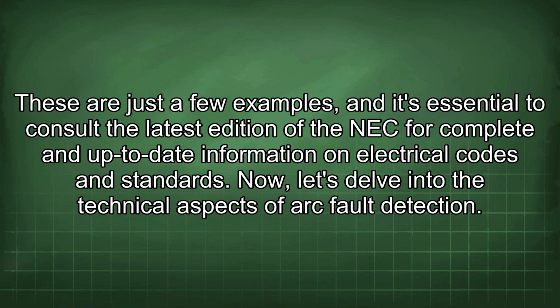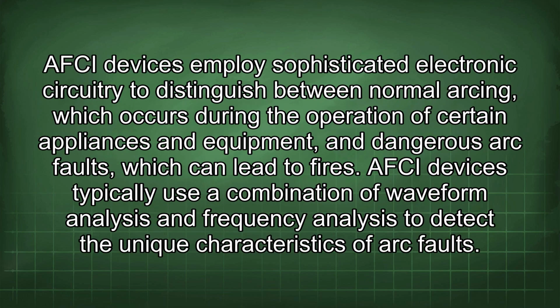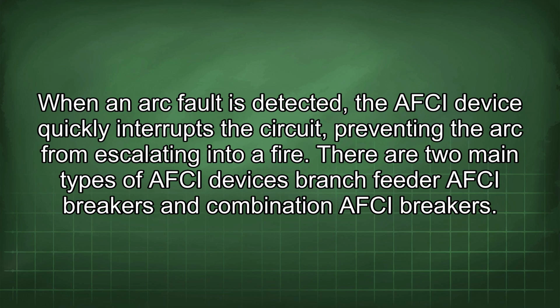Now let's delve into the technical aspects of arc fault detection. AFCI devices employ sophisticated electronic circuitry to distinguish between normal arcing, which occurs during the operation of certain appliances and equipment, and dangerous arc faults, which can lead to fires. AFCI devices typically use a combination of waveform analysis and frequency analysis to detect the unique characteristics of arc faults. When an arc fault is detected, the AFCI device quickly interrupts the circuit, preventing the arc from escalating into a fire.